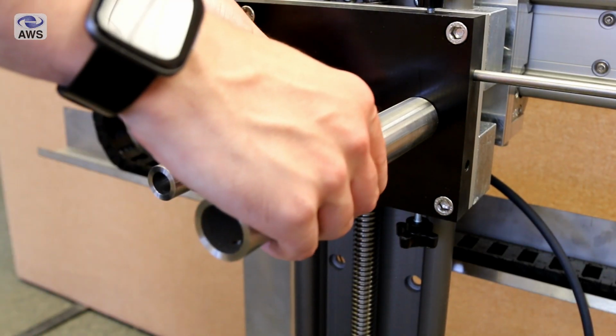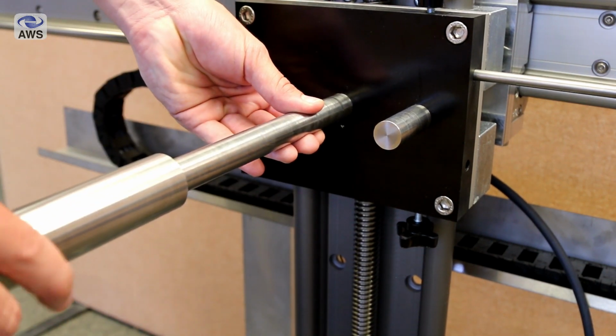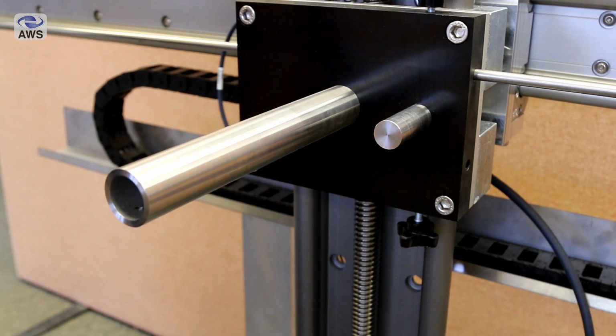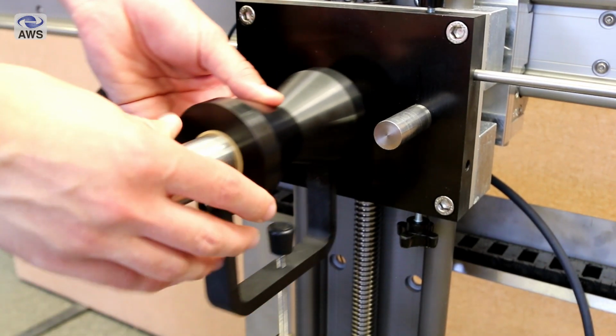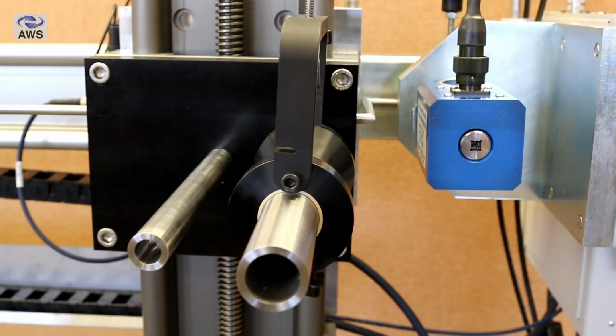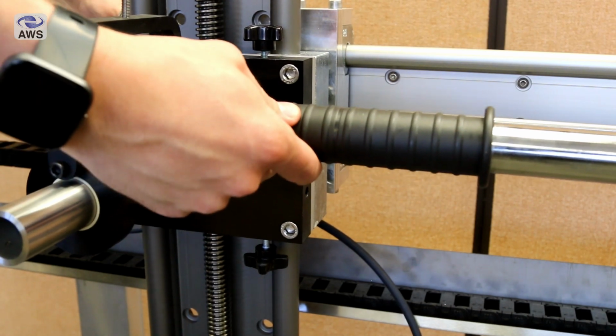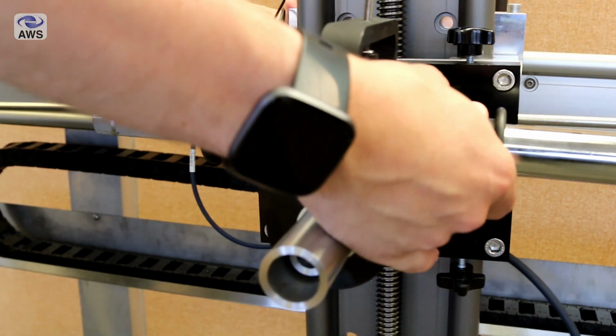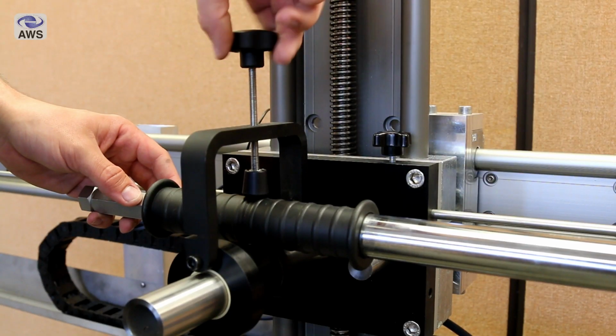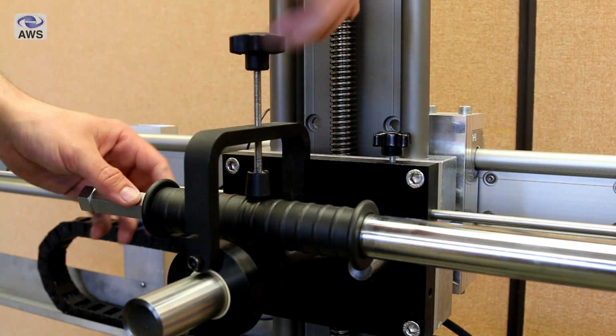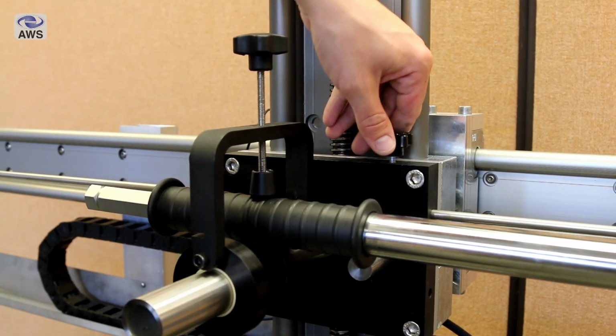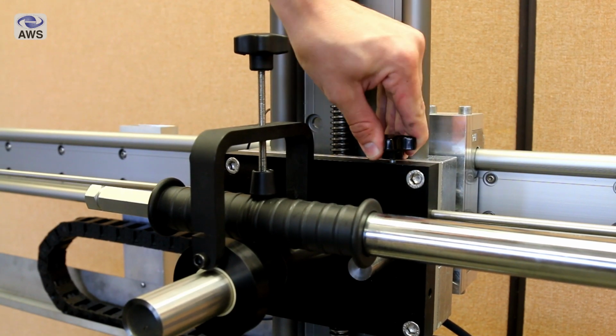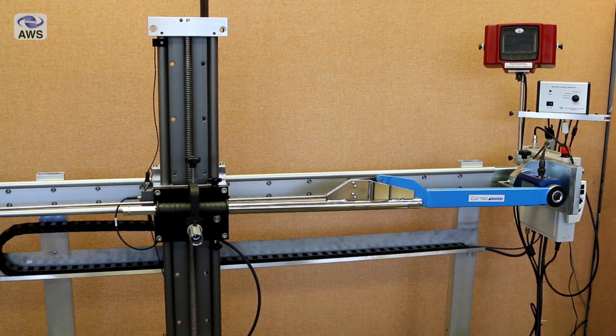There are two reaction pillars on the force application carriage and an outer shaft to swap between them. This means that you can calibrate shorter wrenches on the front pillar and then wrenches of a handle centre length of about 170mm or longer on the centre pillar. Slide the force application carriage along the main track and insert the handle into the centre of the U-clamp. You tighten down the fastening screw on the U-shaped handle, ensuring that the wrench can still slide freely. The machine is now mechanically set up, and this setup is the same for all wrench types: click type, cam type and indicating wrenches such as dial and electronic wrenches.